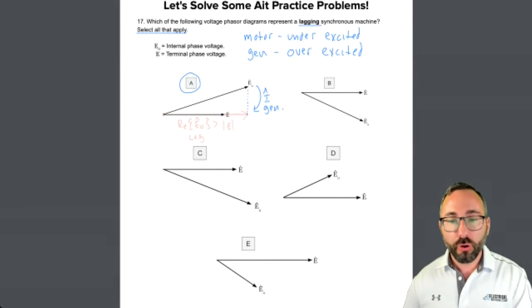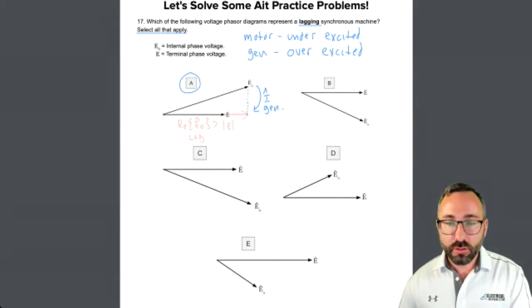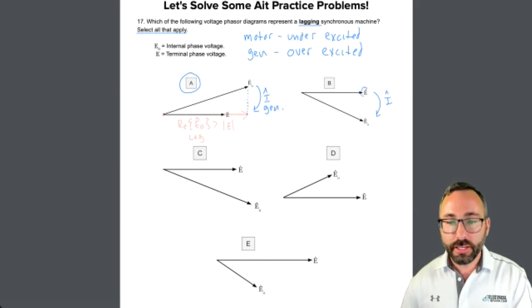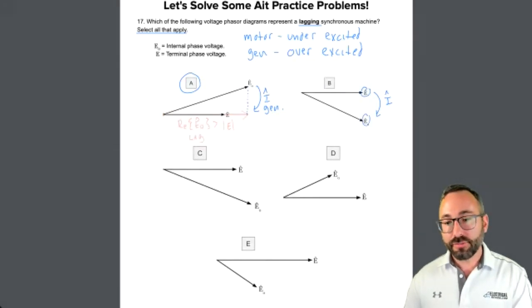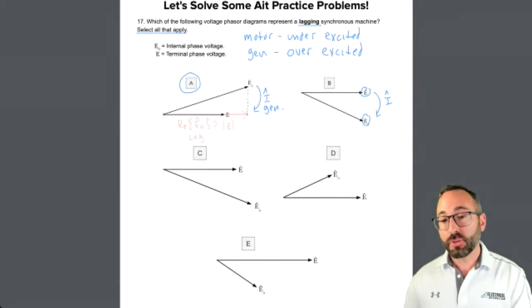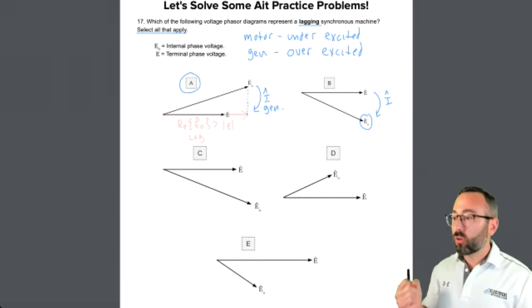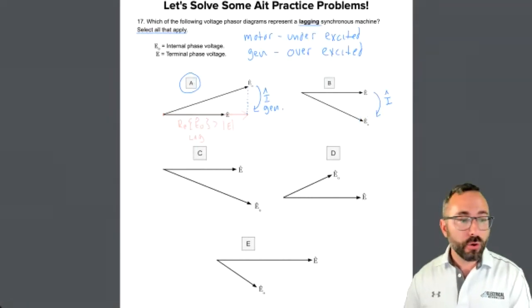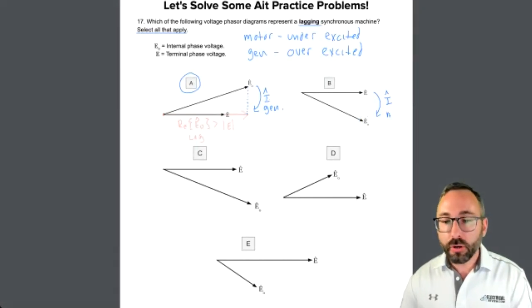All right, B. Is this a motor or a generator? What's the direction of my current flow? Current flows from leading to lagging - this time it's flowing from the terminal connection, where that machine connects to the power supply, to the stator windings. The stator windings EO are drawing that current in. It's got to be a load. It's a motor - B is a motor.